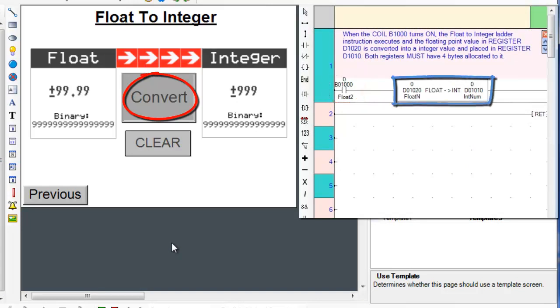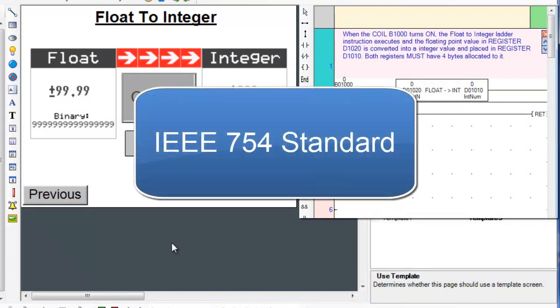the float to integer ladder instruction executes and the floating point value in register D1020, which must have 4 bytes allocated to it, will be converted to an integer value and stored in register D1010, which also must have 4 bytes allocated to it. The floating point value follows the IEEE 754 standard.